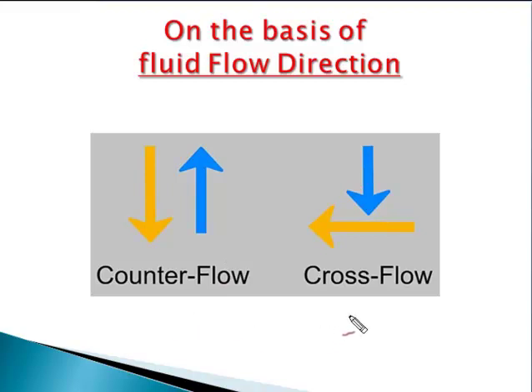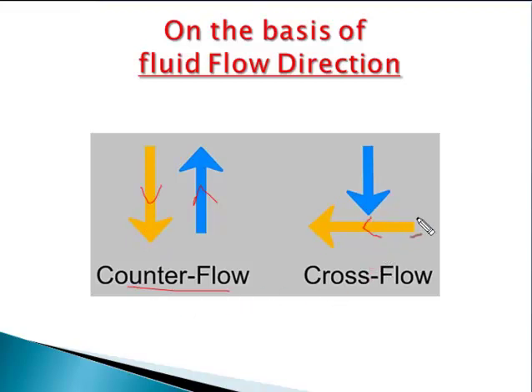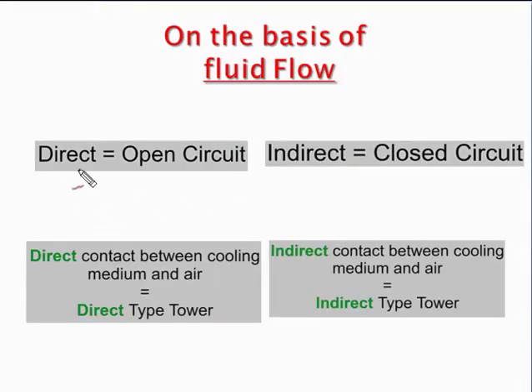On the basis of fluid flow direction, cooling towers are classified into two types: counter flow and cross flow. When hot and cold fluids flow in opposite directions, it is known as counter flow — air flows upward and hot water flows downward. When hot water flows horizontally and air flows vertically from top to bottom, this type is known as cross flow cooling tower. On the basis of contact type, there is direct and indirect type. In a direct type, open circuit is used — air and fluid are mixed together. In an indirect type, both fluids flow through tubes and heat transfer takes place only through surfaces.